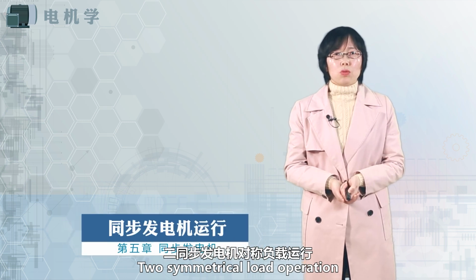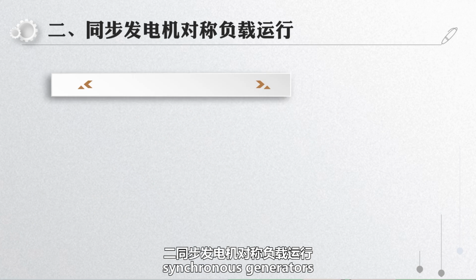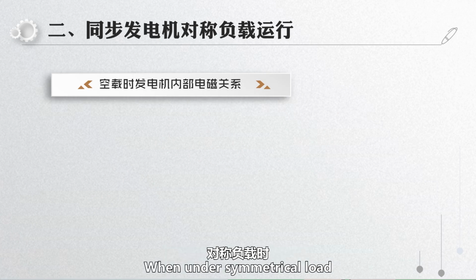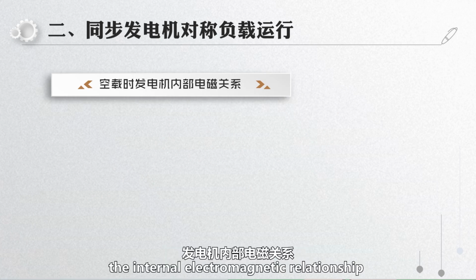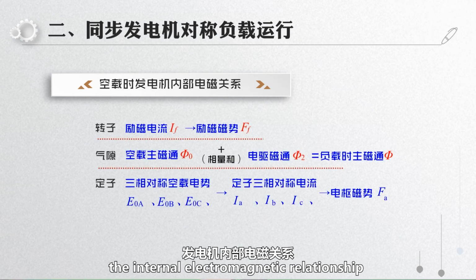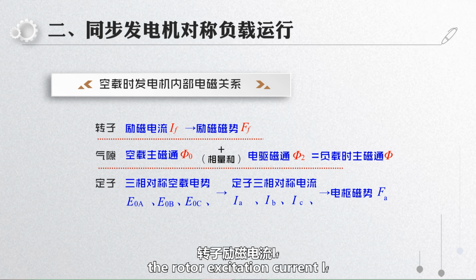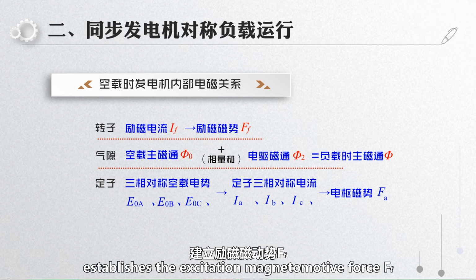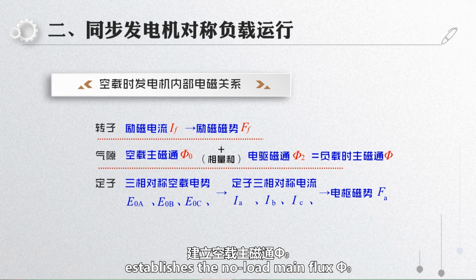2. Symmetrical load operation of synchronous generators. When under symmetrical load, the internal electromagnetic relationship of the generator is such that the rotor excitation current IF establishes the excitation magnetomotive force FF, which establishes the no-load main flux phi0.